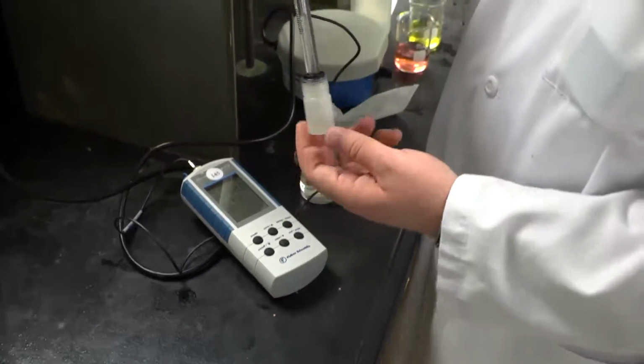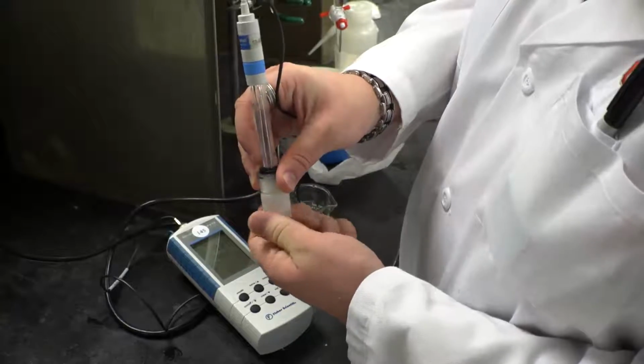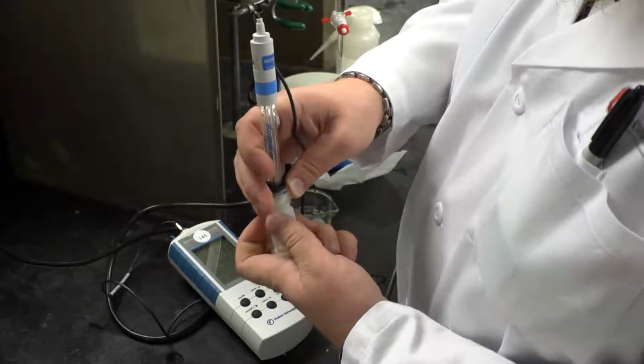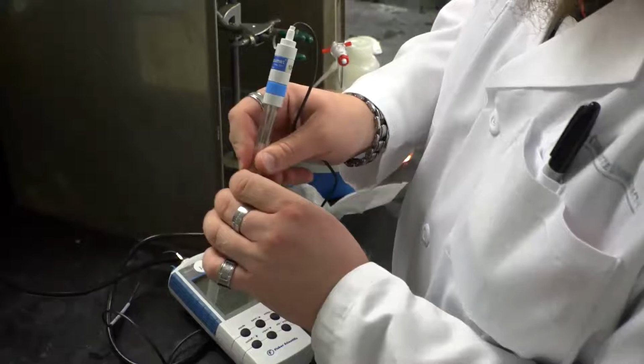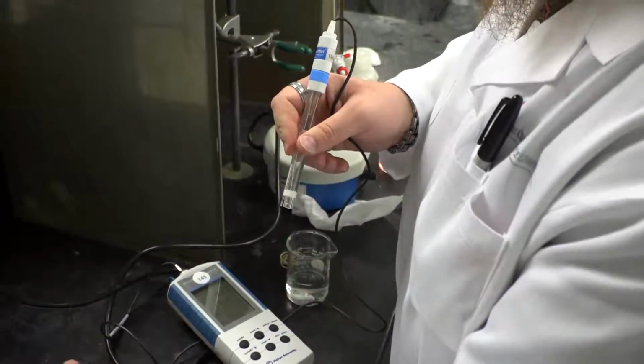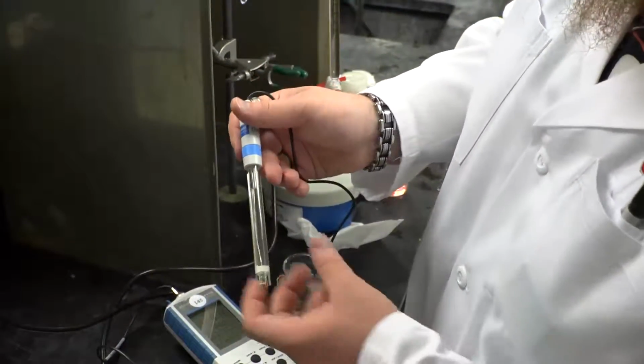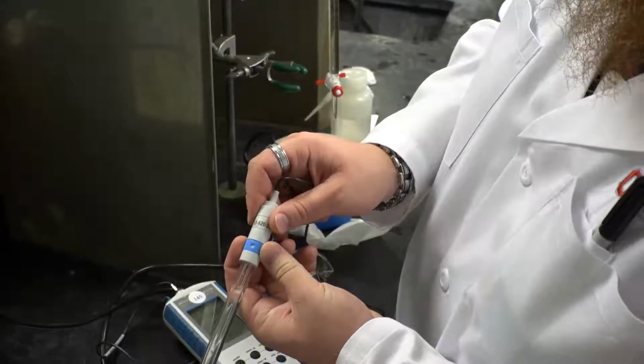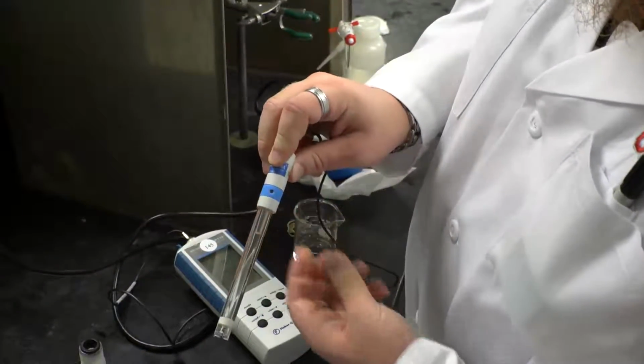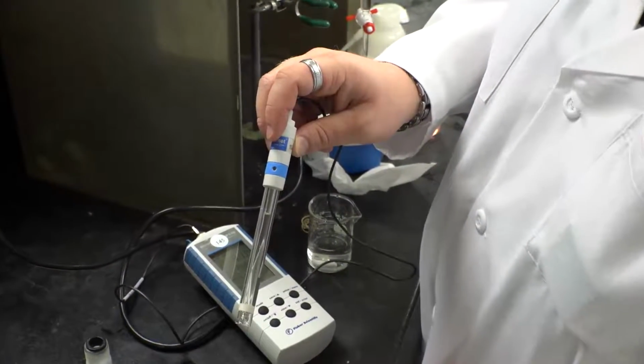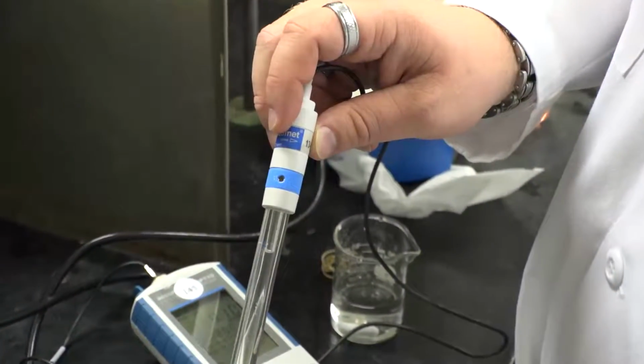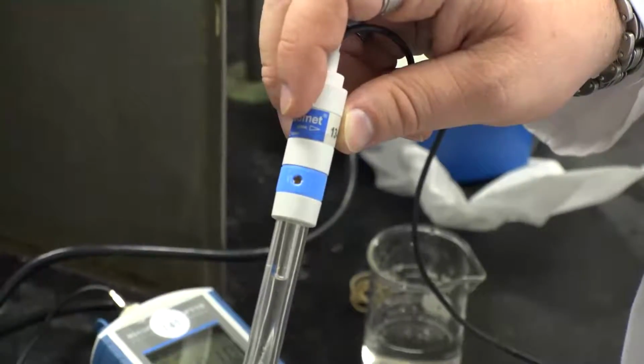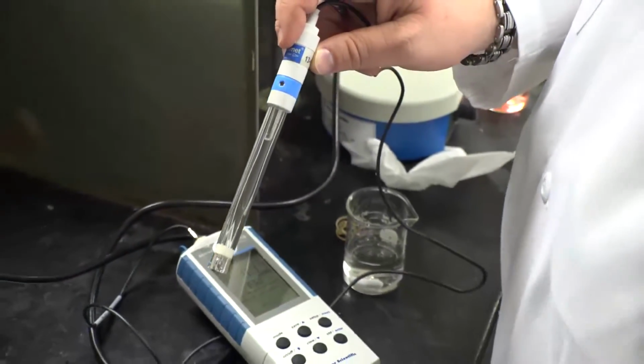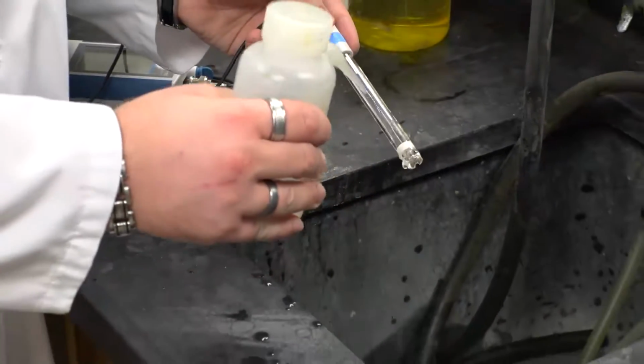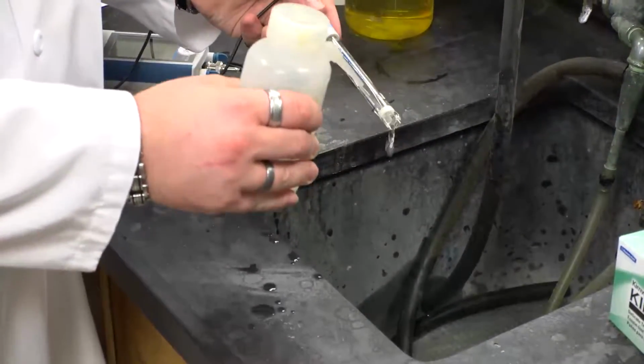After you have obtained your buffer solutions, you may go back to looking at your probe. First, unscrew the cap from the solution the probe is sitting in. Remove the probe from the bottle, leaving the cap on the bottle for future use. Once you have removed the bottle from the probe, look for a plastic ring on the upper portion of the probe and rotate this ring clockwise to the open position. This is to allow the probe to exchange electrons with the air to accommodate for taking measurements with the probe. From there, wash the end of your probe with a little DI water. Blot the end of the probe dry and store it in your pH 4 buffer solution.